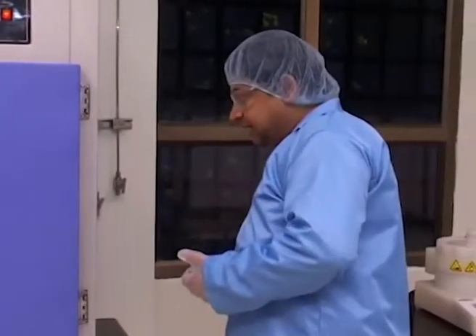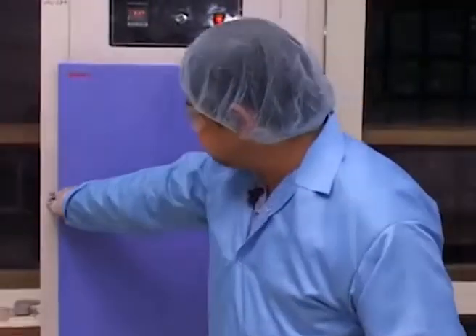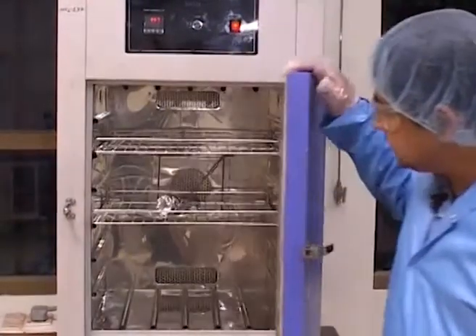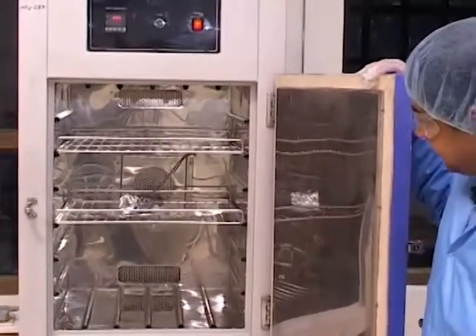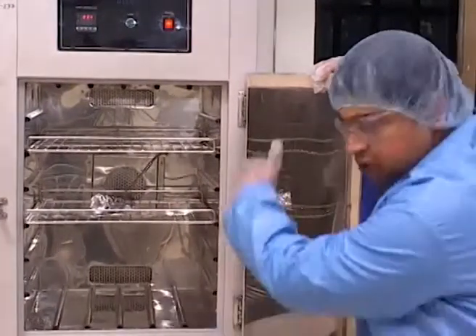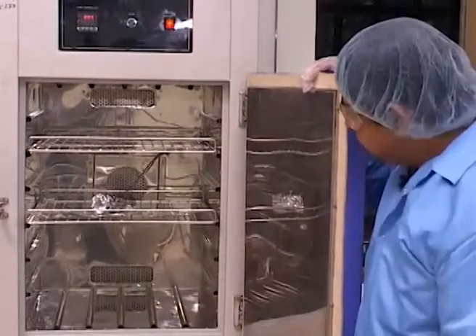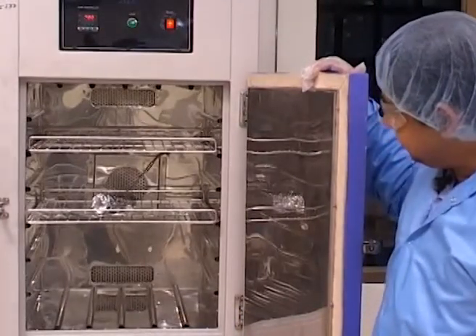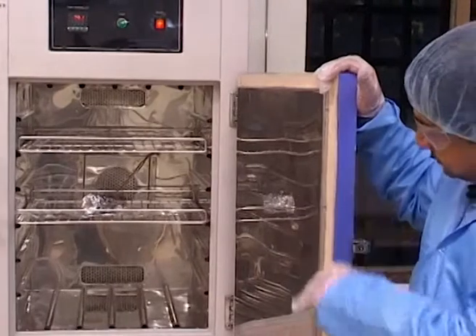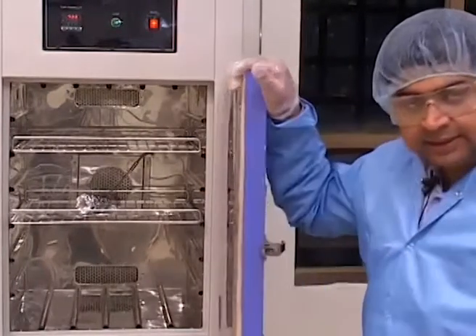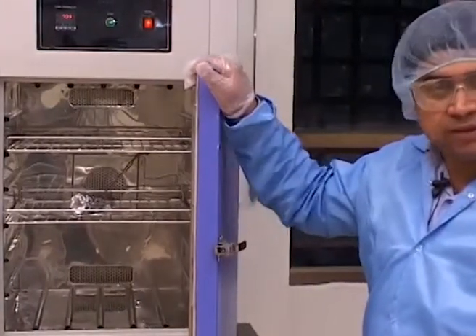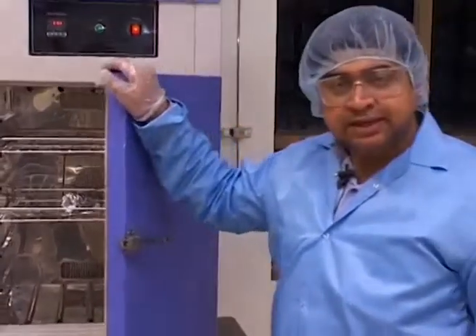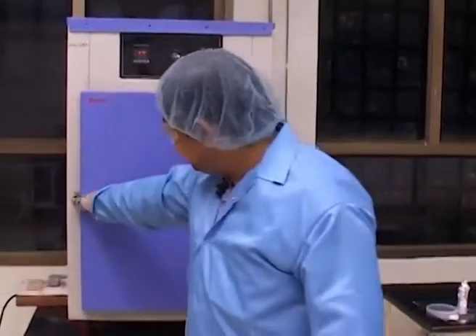So basically, if you look at this oven, really it is a shelved oven. As you can see, there is a fan which actually does forced convection along this whole area, and essentially the wafers are kept at various levels. The thermocouple is somewhere at the bottom. That is one disadvantage of this particular type of oven, because it sometimes is not a very good indicator of the temperature that happens.